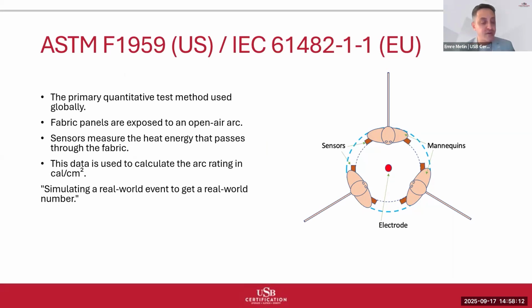Let me walk through the primary quantitative test method used globally for arc flash clothing. Both ASTM in the States and the IEC in Europe use fundamentally the same approach, exposing fabric samples to a controlled open air electric arc and measuring the thermal energy that passes through the material. The test setup involves creating an electrical arc between electrodes positioned at a specific distance from fabric samples mounted on sensor arrays. Multiple sensors behind each fabric sample measure the heat energy that passes through the material during the arc exposure.